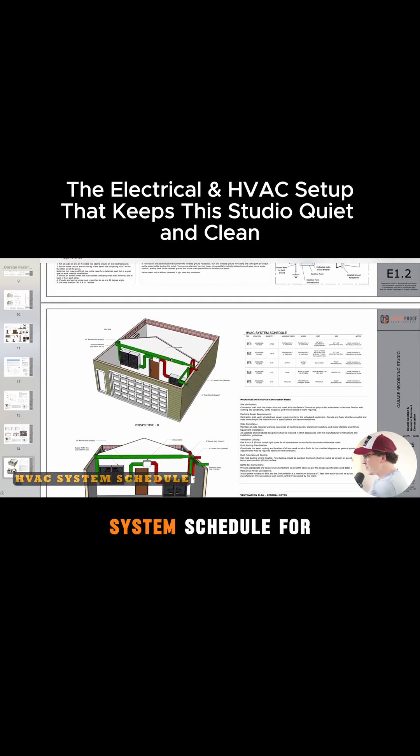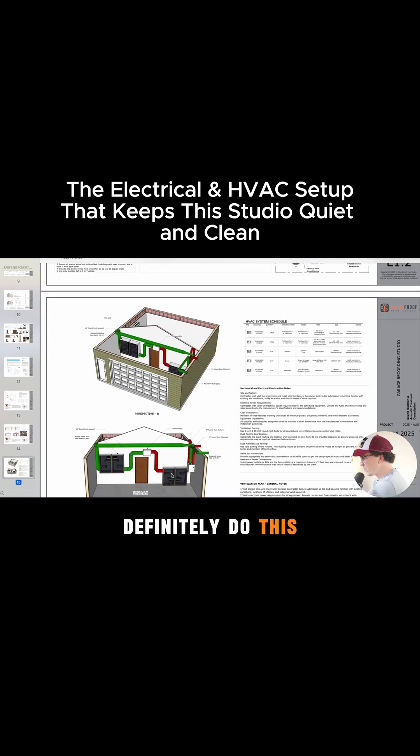The HVAC system schedule is what I've been doing more of, and I'm definitely going to do this for my own system. In humid climates, I like to do the Broan ERV — we've got a 150 CFM ERV here. This is going to be our return baffle box system, and this is going to be our supply. This is the Aprilaire dehumidifier — either the 100 pint or 80 pint should work, depending on your dehumidification needs. This is a separate baffle box system because it is running its own fan, and I don't want to mix it in with this one, increasing CFM loads and the size of our baffle boxes.